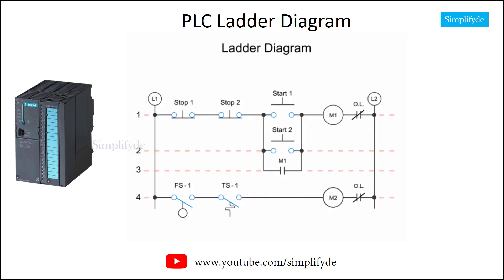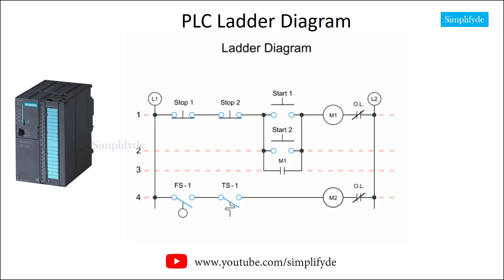When referencing wire segments associated with each rung, you start at the top left and number every wire between contacts. The wire against rail L1 before the stop one contact is wire one, the wire between stop one and the stop two contact is wire two, and so on across the circuit, with each subsequent wire between contacts numbered sequentially. Any contacts in parallel will share the same wire number, so there is no need to number them separately.